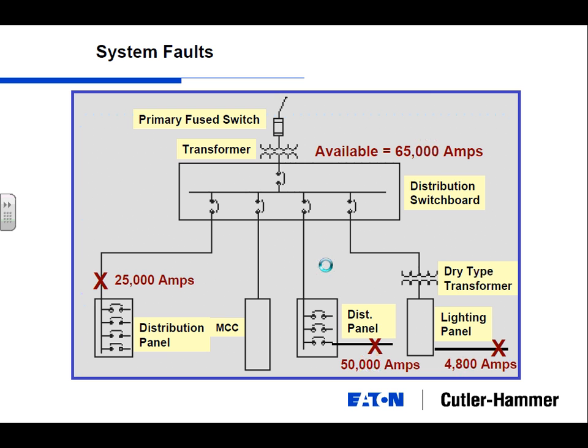And that process has inherent impedance built in because you're not direct connected. There's no direct connection. It's all magnetics between that transformer. So on average, you're looking at about a 5% impedance fixed in right there, and that's probably going to be one of the highest impedances you're going to find in your distribution system.